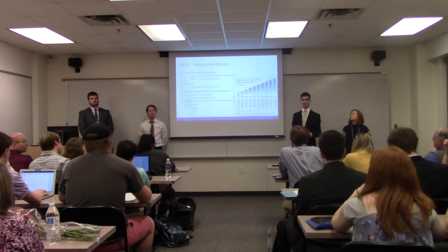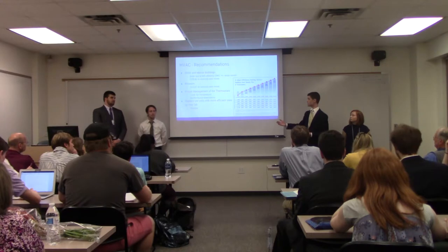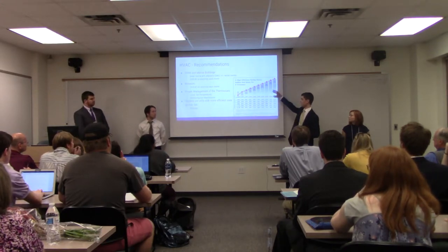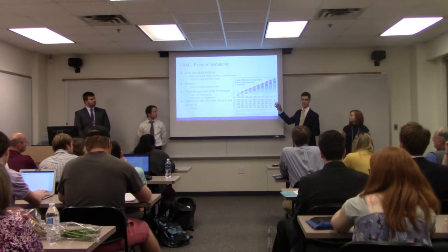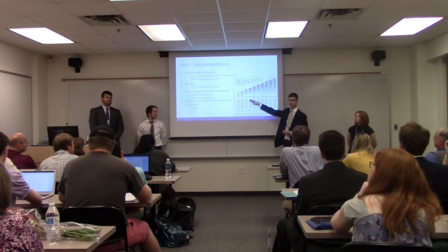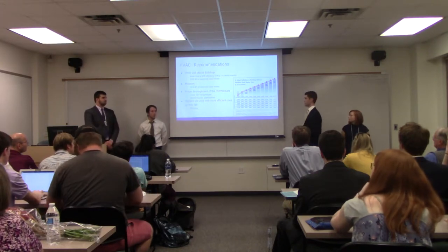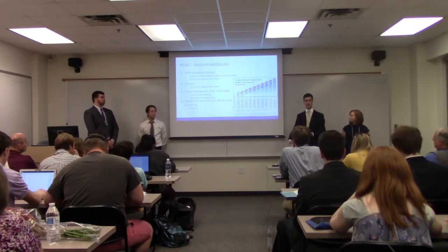It would be wise for the museum to have a proper management plan for paying for replacement units. The SEER ratings for the Smith/Manse and Museum fall between 9 and 10, which is around the national average — slightly lower for Virginia specifically. Going from a SEER 10 to a SEER 16 unit could save about 30% nationwide, so it will eventually be wise to make that investment. We recommend they either put money aside now or plan to spend all at once when units fail.